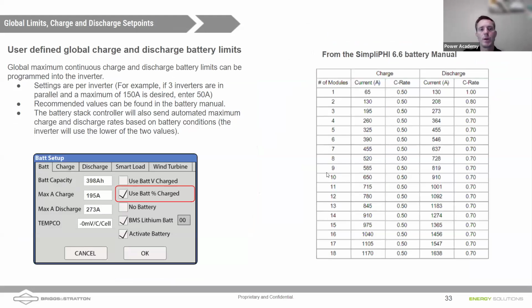I want to point out here, especially with AC coupling, how important it is to make sure that you do not exceed the charge limitations of the battery bank. With AC coupled systems, that AC power is either on or off. And when it's on, the microinverters or the string inverter is pushing as much power as they can. That's the whole job of the inverter, to maximize the output from that solar array.